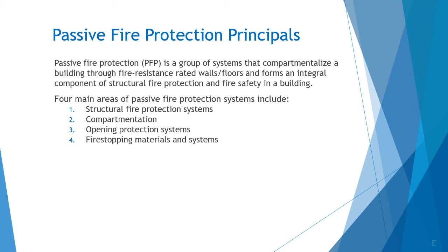Then there's fire stopping and material systems, specifically conduit penetrations - running through that wall while maintaining the separation. A lot of these end up being required to be tested and approved nationally, by nationally recognized testing laboratories like UL and FM. Most every discipline doing construction is going to specify something UL listed, relying on the fact that a third-party test has proven these things function as promised.